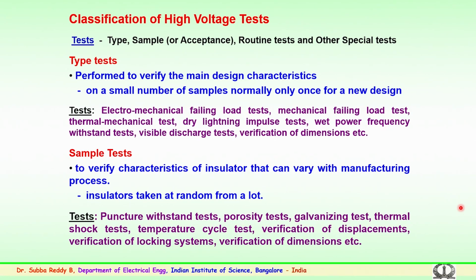Then there is the dry lightning impulse or dry lightning surge test, which is specified for a particular voltage level, then the wet power frequency withstand test. Wet power frequency is a simulation of artificial rain on the insulator strings, to verify whether they can withstand a particular voltage level for a particular duration. This is followed by the visible discharge test, or the corona test.